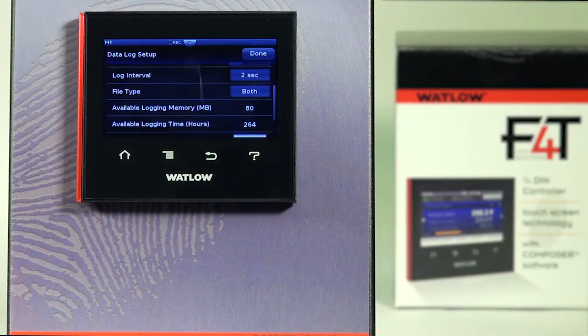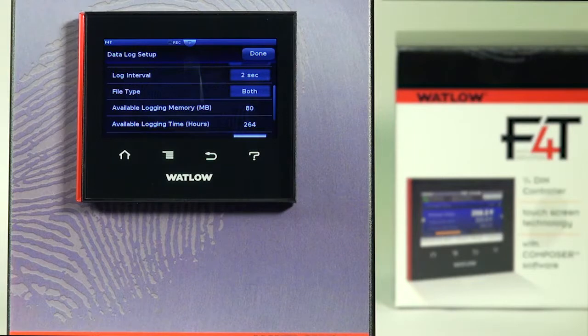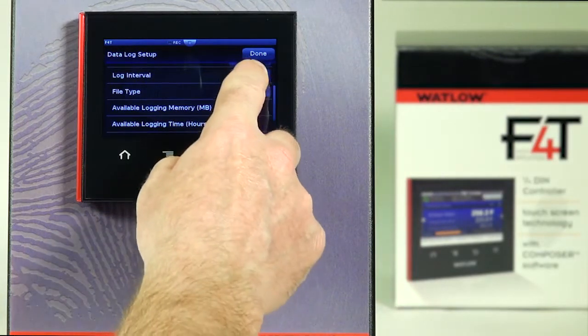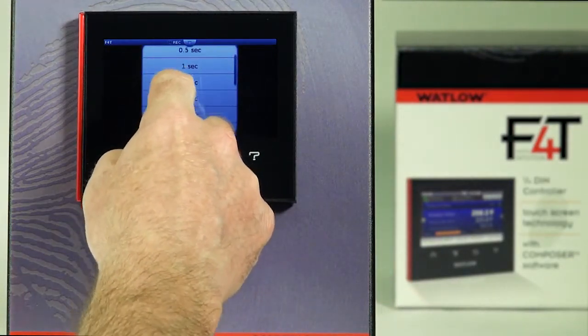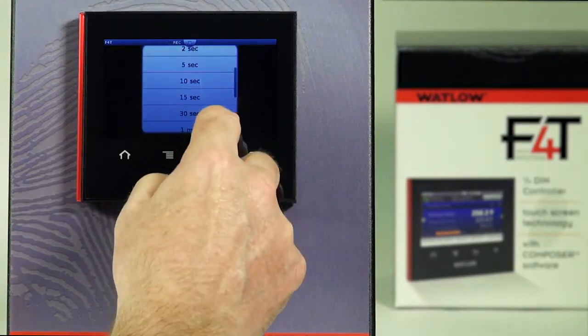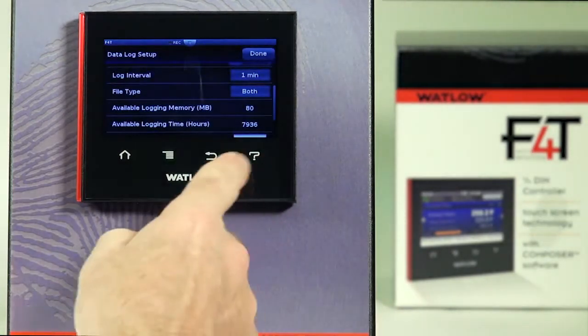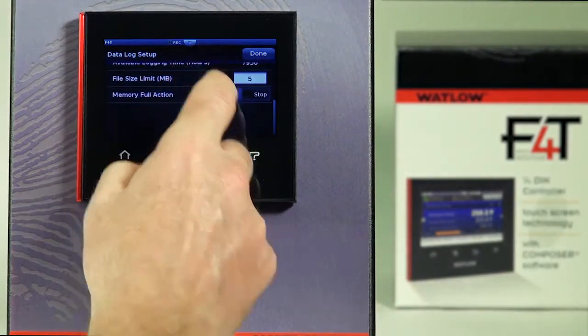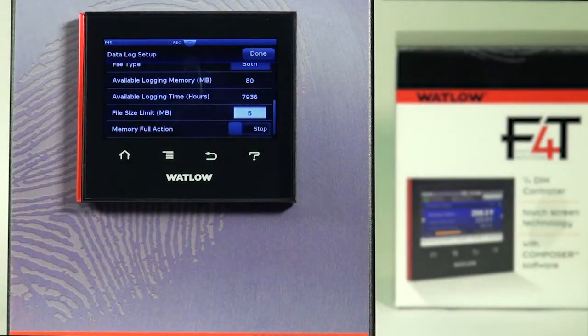'Available Logging Memory' — I mentioned we have 80 megabytes of internal memory. It shows you how much memory is still left, as well as the next parameter expressing it in hours — 264 hours of available time. If that's not enough, you can go back into the log interval — it is a dynamic setting where you can slow down how fast you're recording. Change it to one minute and you can see the available logging time in hours stretches out to almost 8,000 hours.